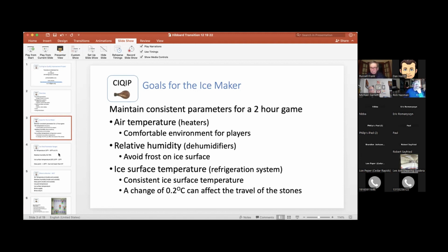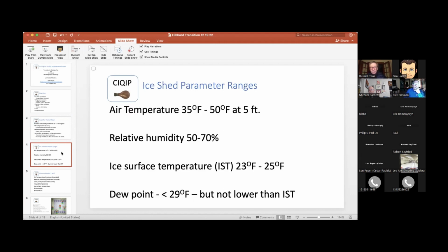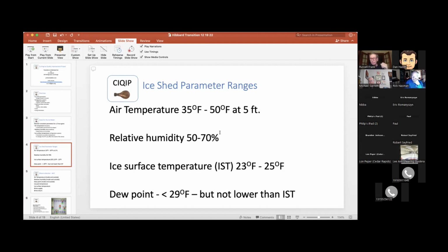Every rink is different. So here are some parameter ranges - Jim and I were just talking about this - and Jim would say 50 to 65% relative humidity. Air temperatures are anywhere from 35 to 50, depending on what club you're in. It really varies from club to club. Ice surface temperature, again, pretty much between 23 and 25, dew point under 29, but not lower than your ice surface temperature, because if it is, you'll start evaporating your ice.